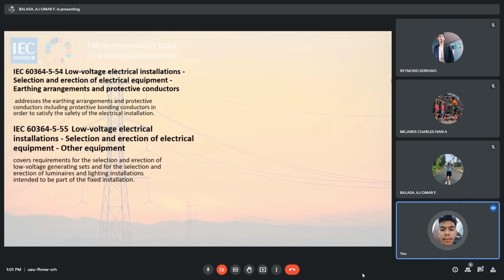IEC 60364 Part 554, earthing arrangements and protective conductors, addresses the earthing arrangements and protective conductors including protective bonding conductors in order to satisfy the safety of the electrical installation. General requirement: the earthing arrangement may be used jointly or separately for protective and functional purposes according to the requirements of the electrical installation. The requirements for protective purposes shall always take precedence. Where provided, earth electrodes within an installation shall be connected to the main earthing terminal using an earthing conductor. Note: an installation does not need to have its own earth electrode.